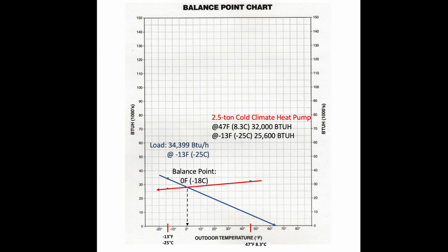here I've used the same load, my load, and I've used my Mitsubishi heat pump data. At 47 or 8.3, I'm getting 32,000 BTUs out of it. And at minus 25, I'm getting 25,600. So you can see where that equipment line crosses the load line. My balance point is down to minus 18C. And that's just a remarkable difference.